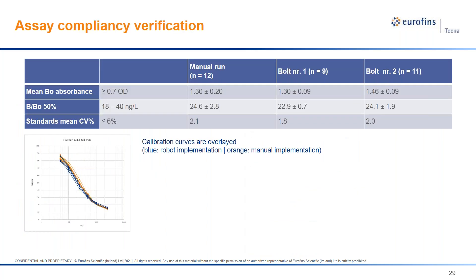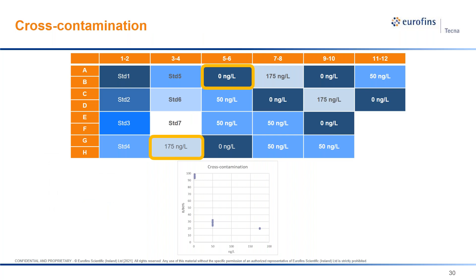The protocol was performing very well. Here at Eurofins Technologies we compared a few manual sessions to those collected by two independent machines and got not only compliant results in terms of signal intensity, curve positioning and pipetting precision, but more in general a very compact group of sessions with overlaid calibration curves. Also, standards in this kit are made of milk, so running the curve is not sufficient. The Bolt operates with one single pin for all pipetting steps — on one hand this saves a lot of disposable plastic tips, but on the other hand it may pose a risk of performance variability if the pin is not properly washed after every step.